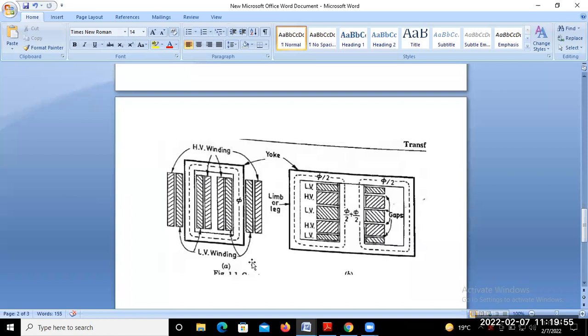If you want to know overall which type of material is used in the core of the transformer, we are concerned about core losses. I think you are familiar with the term core losses. We want to reduce core losses so that the efficiency of the transformer is improved. So for the reduction of core losses, we try to use CRGO material as the core material of the transformer.